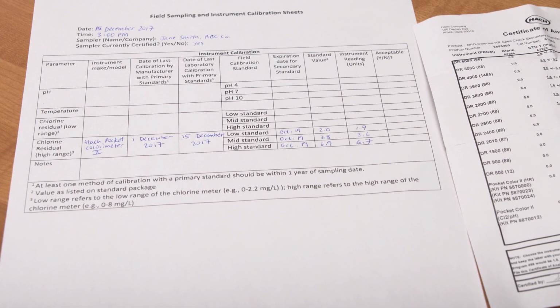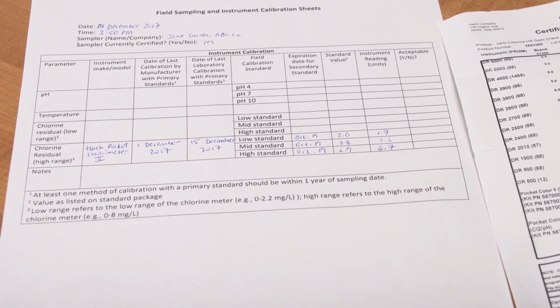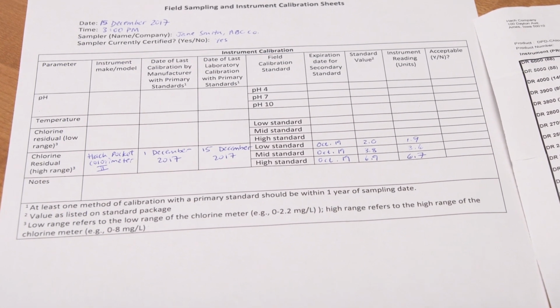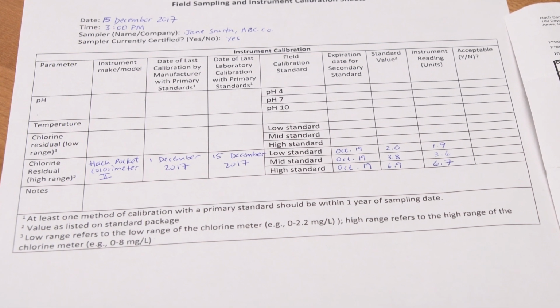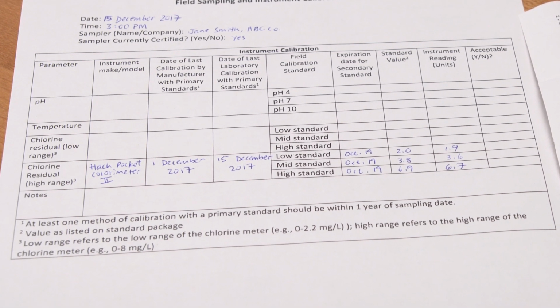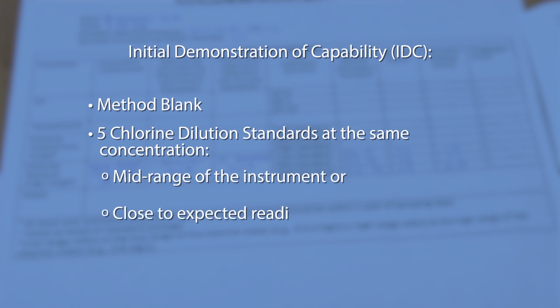If you have never performed an initial demonstration of capability for your instrument, you will need to perform this procedure once for each instrument that you use. If you have different people using chlorine instruments, each person should perform an IDC for each type of instrument that they use. The initial demonstration of capability consists of doing a method blank, 5 replicate dilution standards at the same concentration using either mid-range of the instrument or close to expected readings.